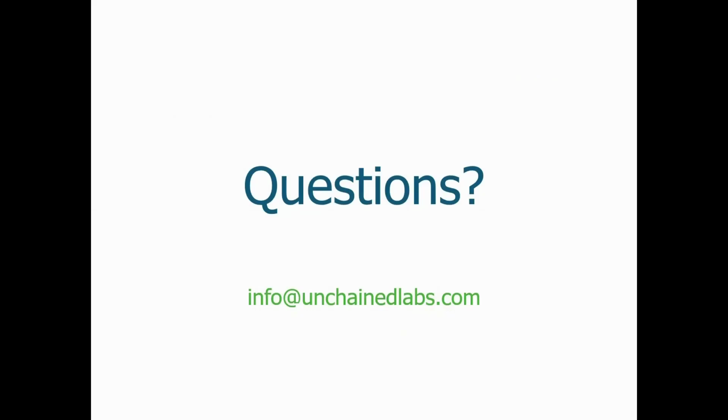All right. This question is a bit more specific, from Braylon. Does UNCLE have tools for 21 CFR Part 11 compliance? It does, yes. We can both provide installation and operational qualification of the instrument itself, and then there is a mode to the software that uses an audit trail and is ready to be used in a 21 CFR Part 11 compliant environment. So the tools for that are part of both the hardware and also the UNCLE software.